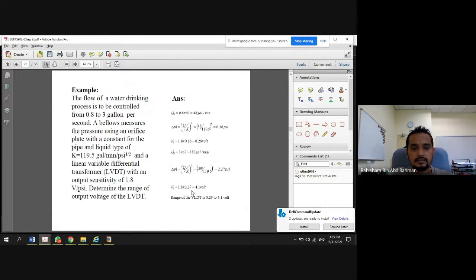Rearrange this formula, and be careful of the unit, gallon per minute per PSI. Okay, then you can calculate what is the range of the LVDT. And from this example, by using the same formula, you can calculate what is the minimum gallon per second on section A and B. You can calculate many things just based on this formula.